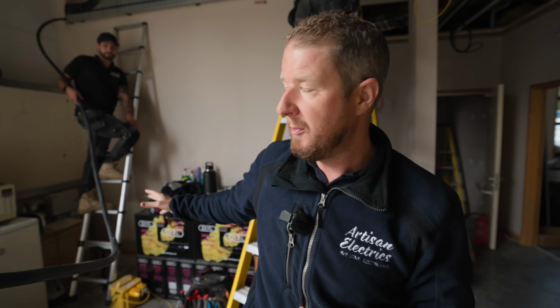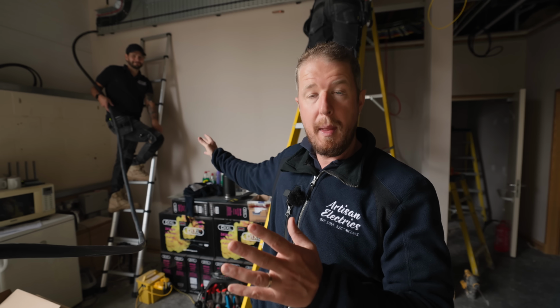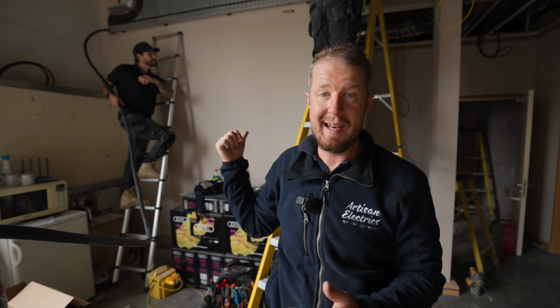So this system works slightly differently to the Sigen store system we install in residential situations, where you've got a gateway. In this situation you can fit a gateway, but that's really for massive systems. If you've got up to 3 inverters, you can actually use the inverters as the gateway, and that's what we're doing here. This 35mm armoured cable is going to run from the mains incomer to the inverter, through the inverter and back to our main distribution board, providing full low latency backup for the entire building.